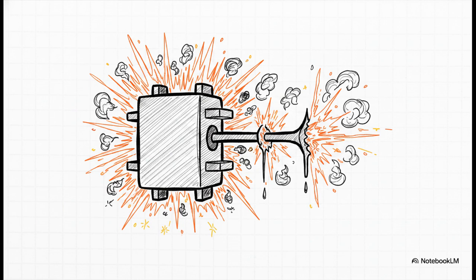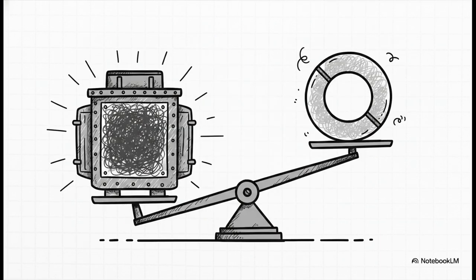Never short-circuit the secondary of an energized VT. Because voltage transformers are proportional voltage devices, shorting them out allows the current to flow completely unrestricted. Damaging, massive currents will surge through that secondary circuit, quickly melting wires and entirely destroying the transformer. Okay, let's relieve some technical anxiety with Rule 3.